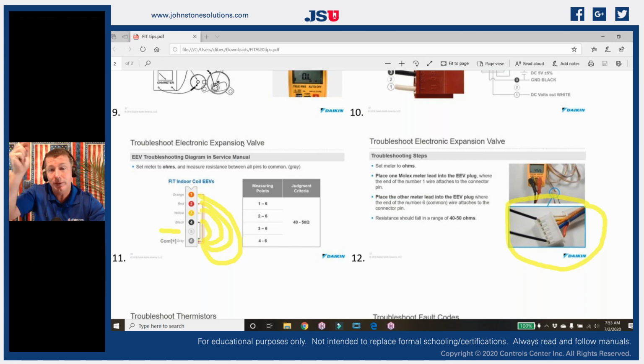And if one of them is off from the others, then we can't complete our sequence. Our 1, 2, 3, 4, 1, 2, 3. We can't complete that. So we just simply check the power head to see if our power head is actually good. And that will tell us a lot about the operating of the system. Because if I check all 4 of those and one of them is bad, there's no reason to dive into the refrigerant side of the system. I'm just simply going to go get a new power head, replace the power head, and see if that has now solved my issue.